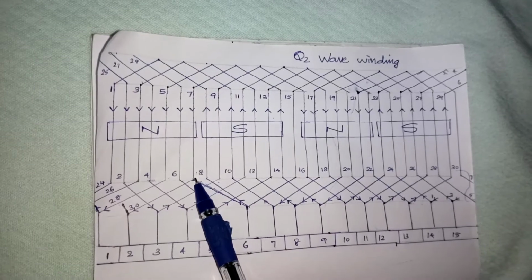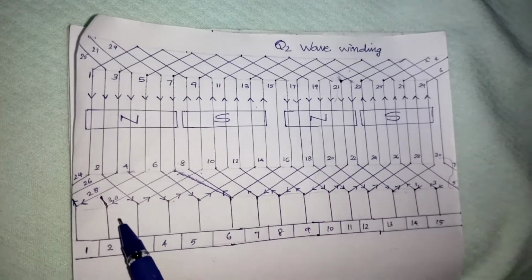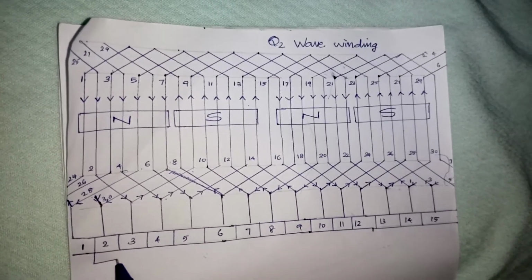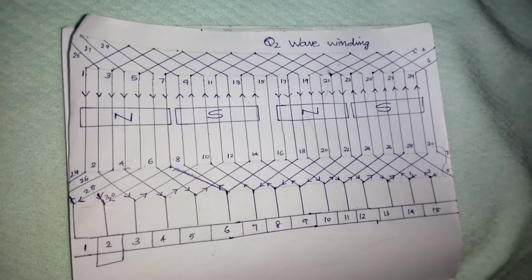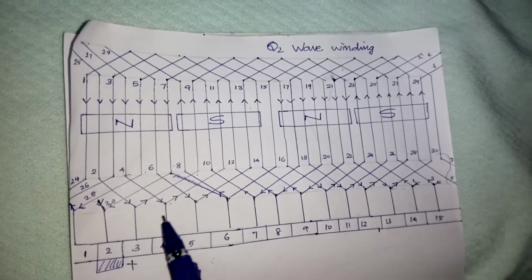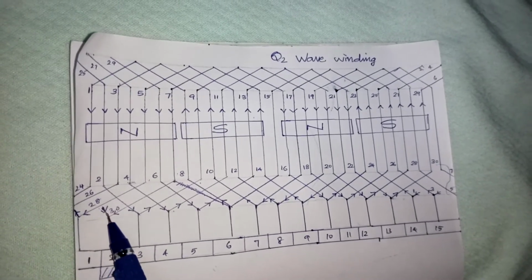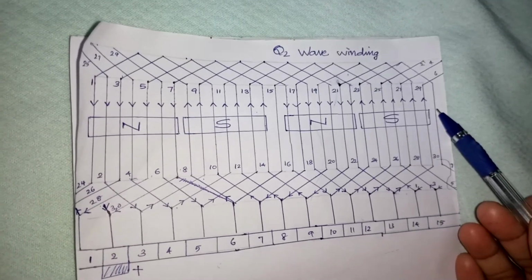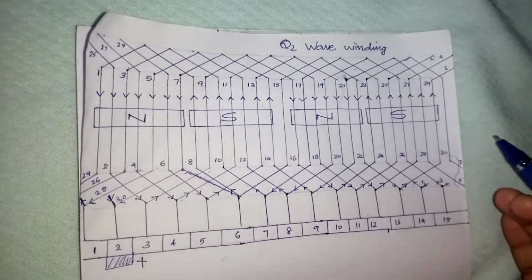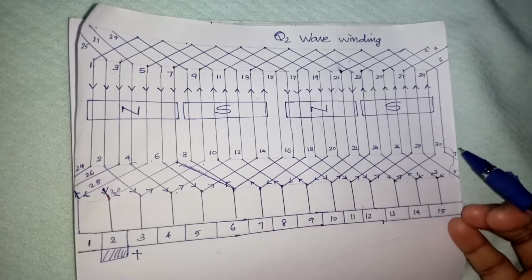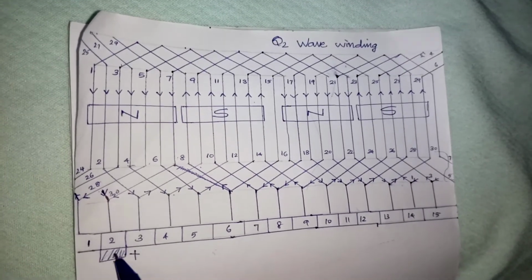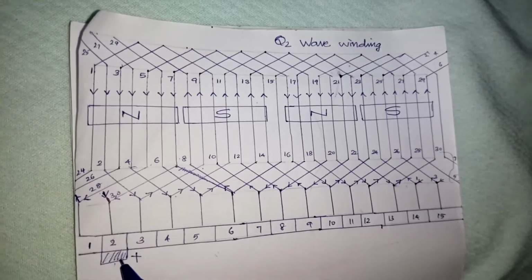The direction of current for the 7th conductor is downward, so we can assume that the direction of current through the 30th conductor is downward, so that we can fix a brush at the second commutator segment. Okay, the direction of current is downward, so we can say that it is a positive brush. Now we are fixing the direction of current in the 30th conductor as downward. That means the 30th conductor is coming under the north pole, that is, the effect of the pole on the 30th conductor is north pole. We assume the direction of current is downward, so fix a brush here. Both currents are coming downward, so that is a positive brush.